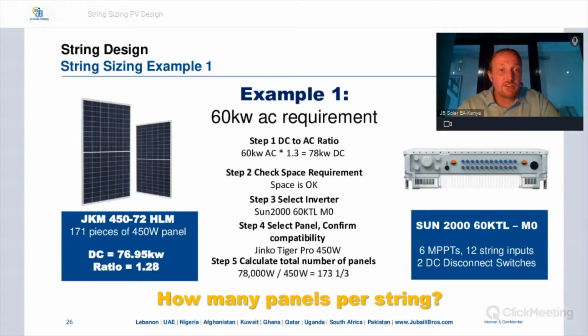Step number 4 is you select the panel and you confirm the compatibility. So we have selected the Jinko 450 watt panel, and we have to check the compatibility like I showed you. We compare the data sheets. We look at the max current per MPPT and the voltage, and we have checked it, and it works, and it's okay. So now step 5 is you calculate the total number of panels. Remember, our DC requirement is 78 kilowatts. So we do 78,000 watts divided by 450 watts, because that's the size of our panel. And the result is 173 1/3. So ideally, that's the number, 173 1/3 panels.